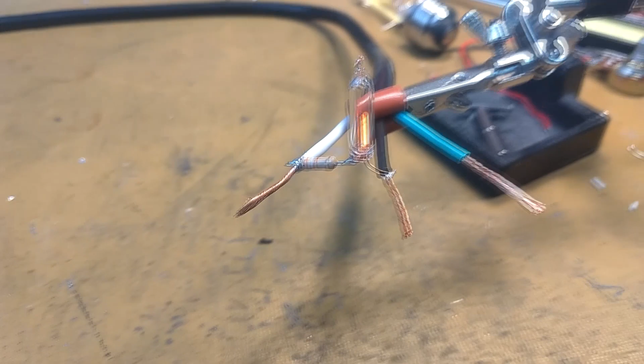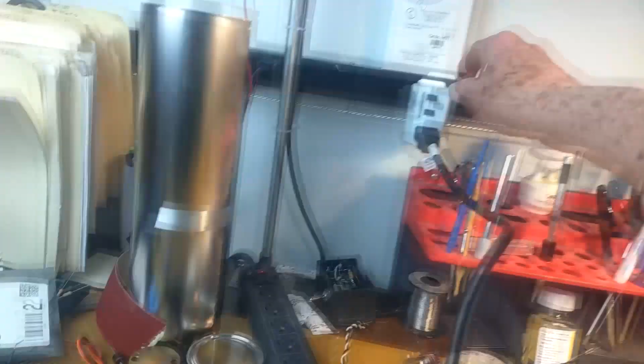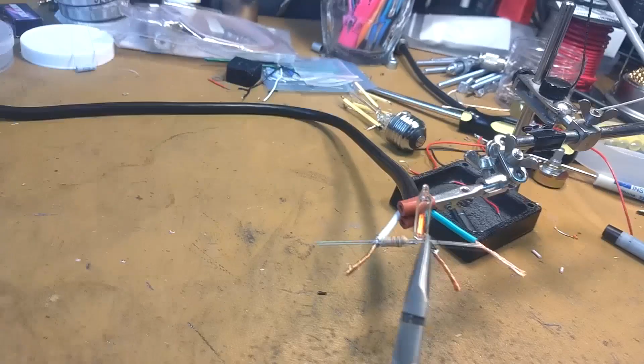and right here I have a 1000 ohm resistor which I'm going to connect between ground and the hot lead. And you see the power is instantly disconnected by the ground fault circuit interrupter. So I'm going to reset that again, and you see we have power. Now, what if you get between the hot wire and the neutral wire? Well, I think you can tell you don't want that to happen.